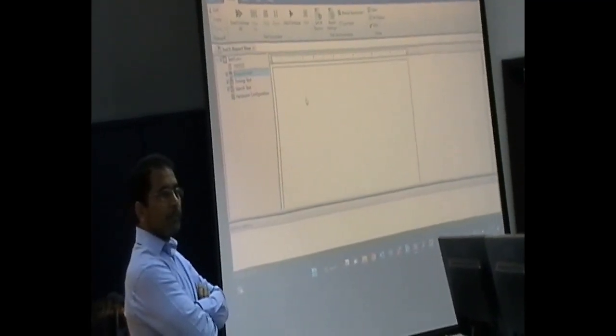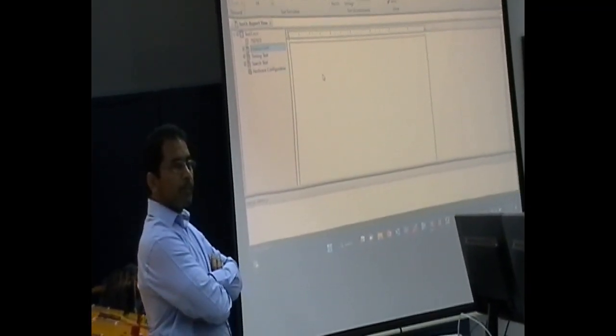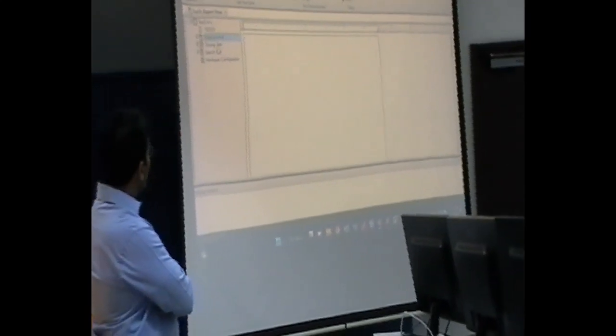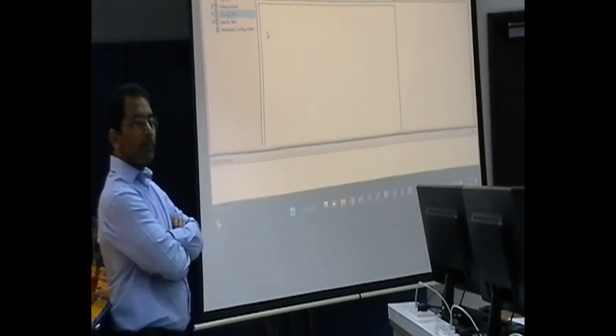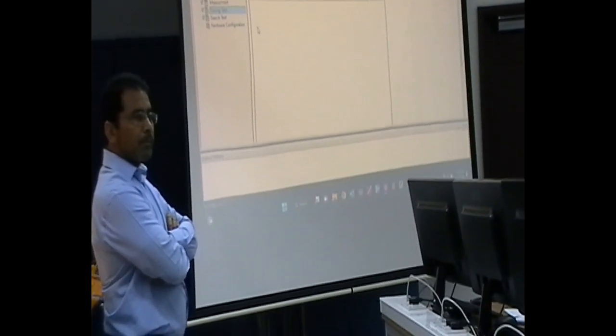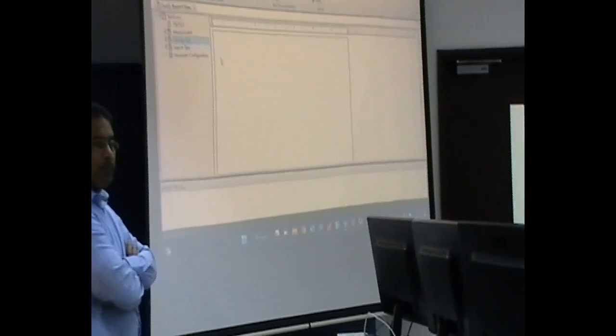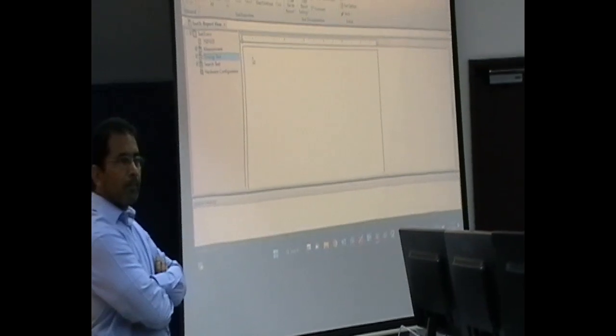We have 3 types again of the test. I want to check the measurement to make sure that the relay CT and VT connection and setting is correct. So first I'll check the measurement. The second one is the timing. I have 0 second for zone 1 and 400 milliseconds for zone 2 and 1.2 for zone 3. I have to check whether it's really operating in like 0 second, otherwise it will take a little bit of time. And the same goes for zone 2 and zone 3. Usually during annual maintenance we'll only do measurement and maybe timing, which we also call a shot test, because I just want one shot and I'll take the feedback from it.